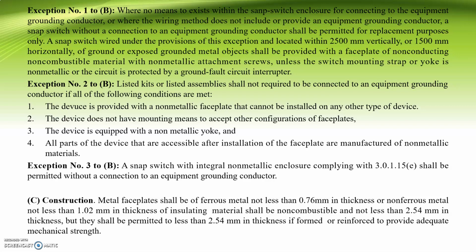So a snap switch wired under the provision of these exceptions and located within 2500 mm vertically or 1500 mm horizontally of ground or exposed grounded metal objects shall be provided with faceplates of non-conducting, non-combustible material with non-metallic attachment screws, unless the switch mounting strap or yoke is non-metallic or the circuit is protected by a ground fault circuit interrupter.